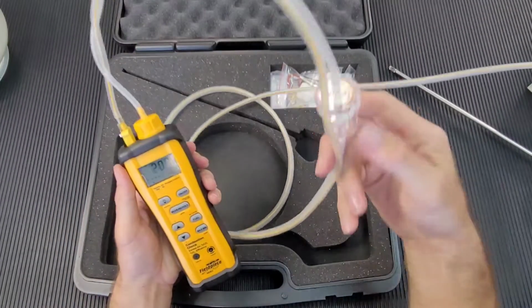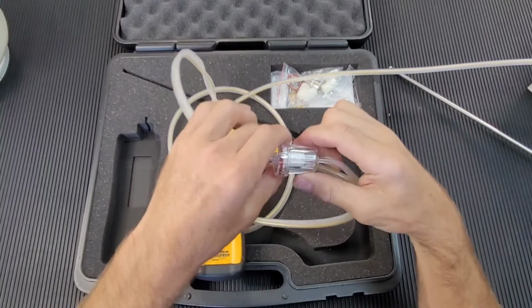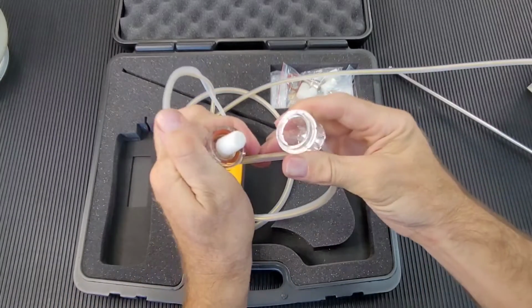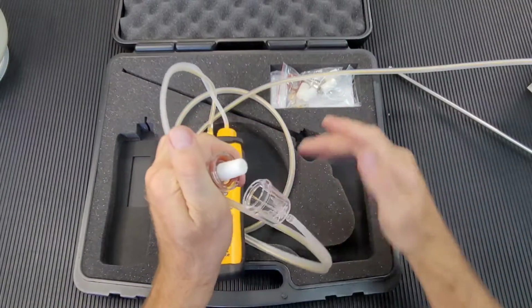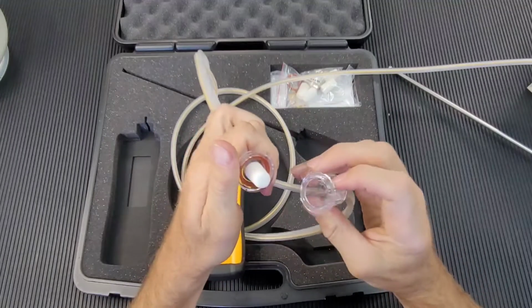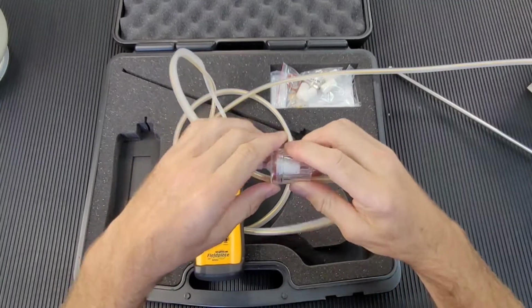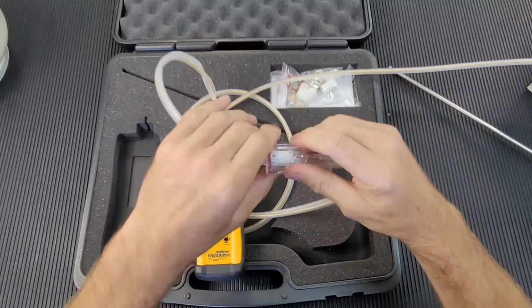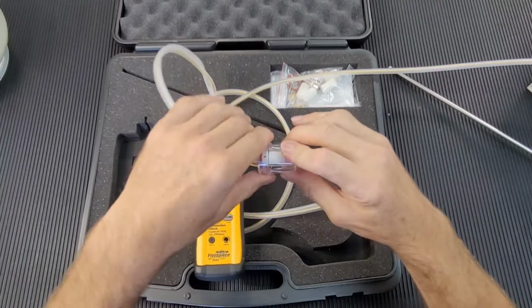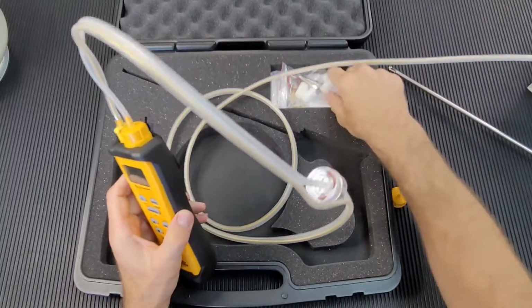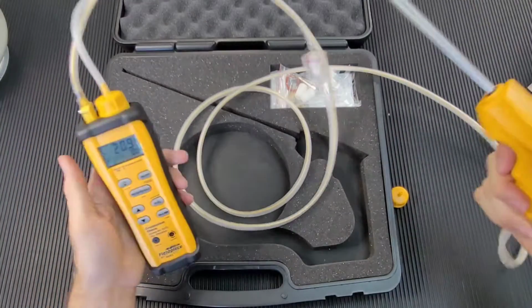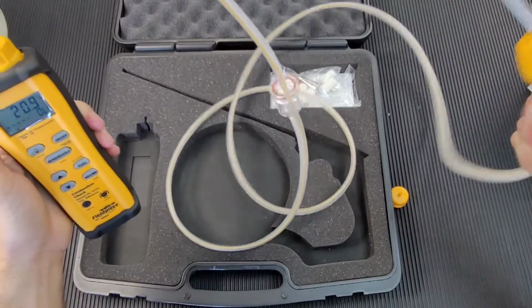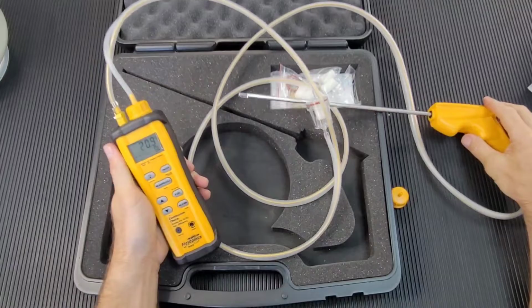Okay, now we have our water trap and filter, which comes off quite nicely right over here. We have extra filters in the accessories and a nice thick O-ring there to make sure no diluted air comes in or gets leaked in. That would give us erroneous data points. Okay, folks, and that's basically the setup. Bang, bang, you're good to go. And that's how you take your combustion measurement and analysis.